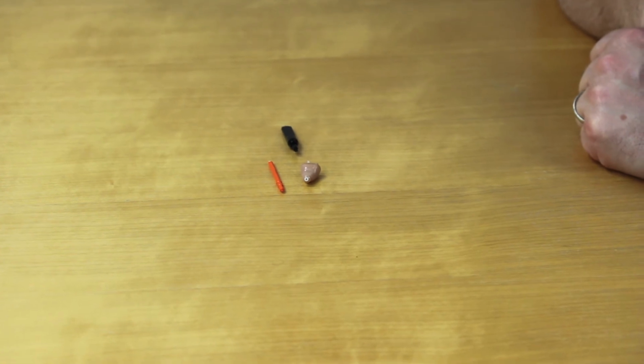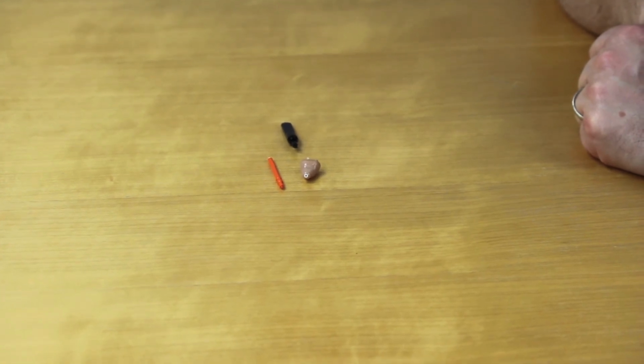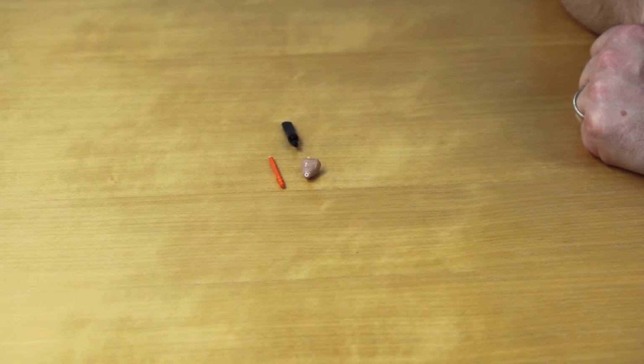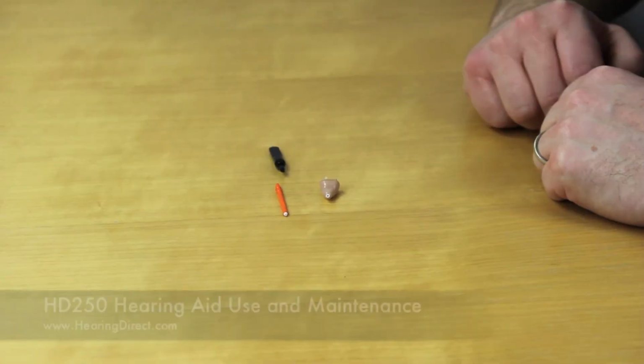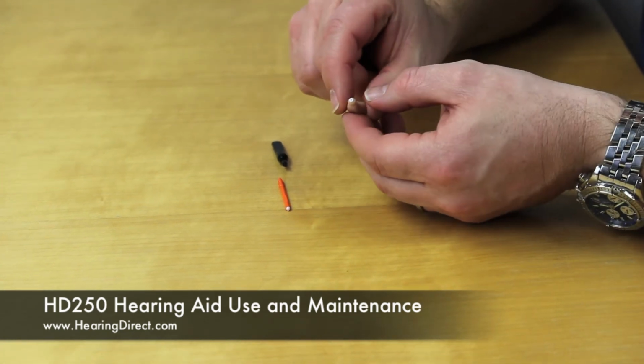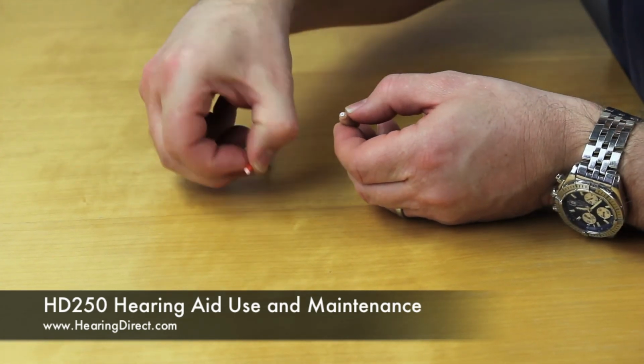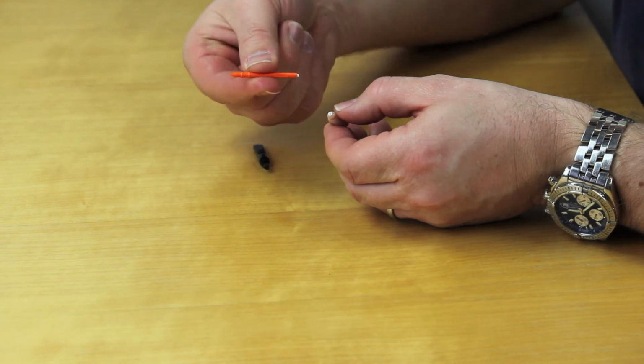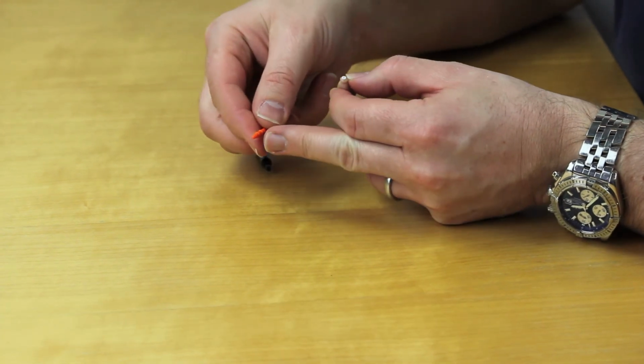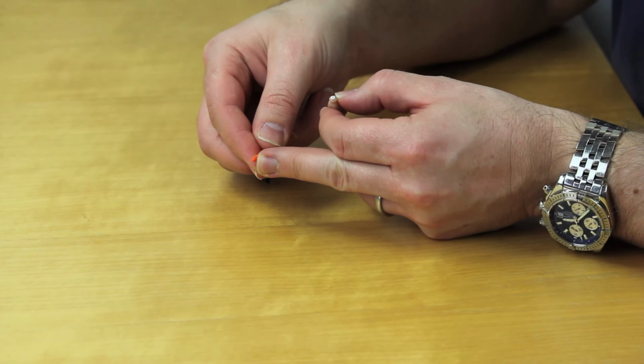If the hearing aid is weak or silent, or if wax in the wax guard cannot be brushed away, then it's time to change the wax guard. The HD250 uses a Hear Clear wax guard system. Each filter is housed on a small wand with a raised point at one end that may be used to remove the old wax guard.